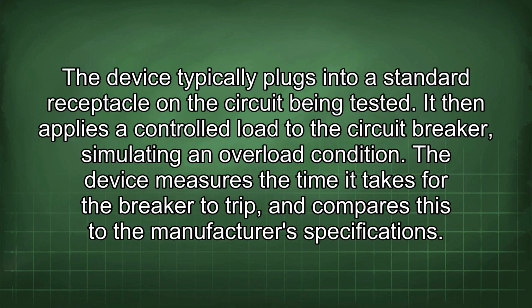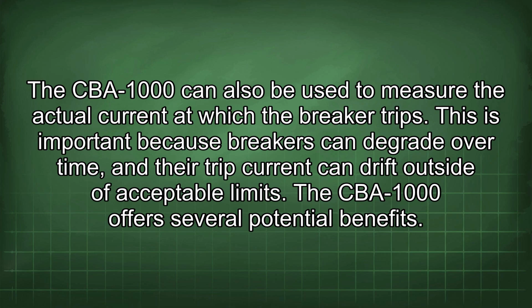The device typically plugs into a standard receptacle on the circuit being tested. It then applies a controlled load to the circuit breaker, simulating an overload condition. The device measures the time it takes for the breaker to trip and compares this to the manufacturer's specifications. The CBA-1000 can also be used to measure the actual current at which the breaker trips. This is important because breakers can degrade over time, and their trip current can drift outside of acceptable limits.